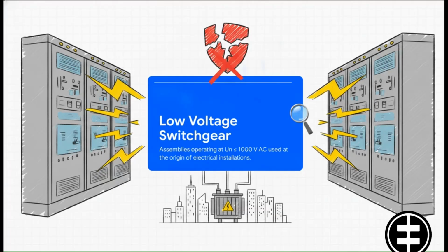Okay, let's start with the basics. Low-voltage switchgear and control gear assemblies operate at voltages up to 1,000 volts AC. These are positioned at the very origin of an electrical installation. Think of the main switchboards in a transformer area, or those massive main distribution boards hidden away in the technical room of a skyscraper. They manage the massive influx of power entering commercial buildings and substations. And trust me, when something goes wrong here, the consequences are completely disastrous.